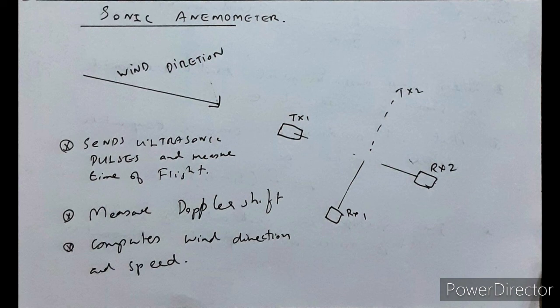There are two transmitters and two receivers placed perpendicular to each other, each transmitting at different frequencies and received at the receiver. The time of flight is fixed, but instead the Doppler shift is measured. According to the Doppler shift in the x and y axes, this gives a wind profile in a two-dimensional plane, including wind direction and wind profiles. A very simple instrument.